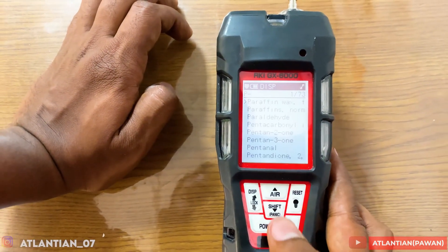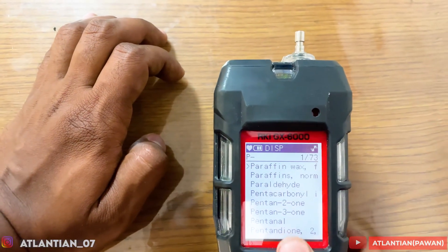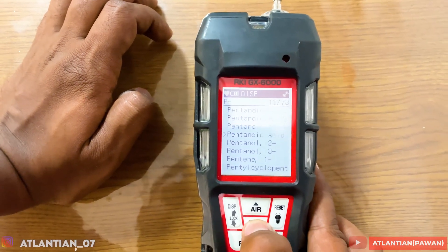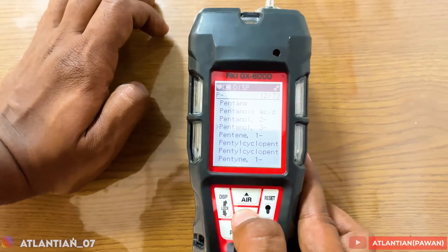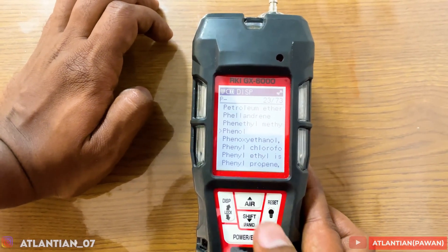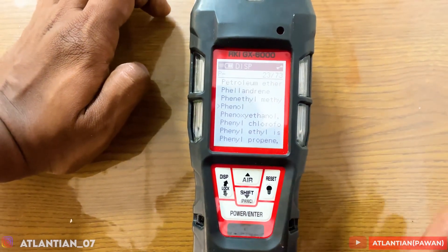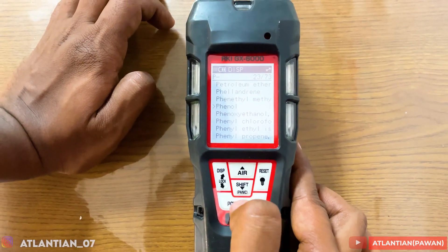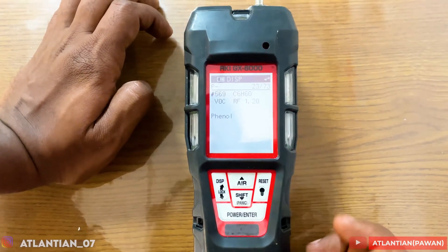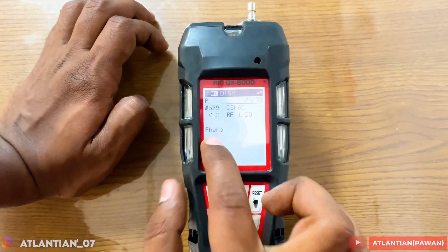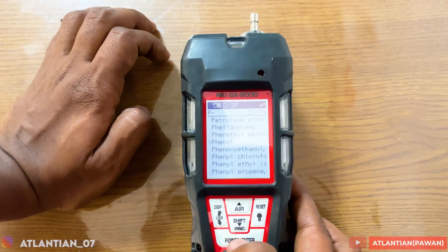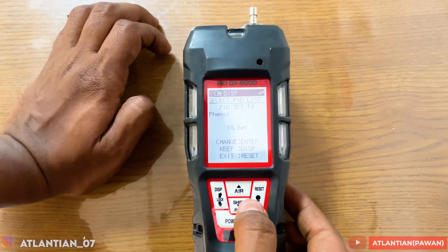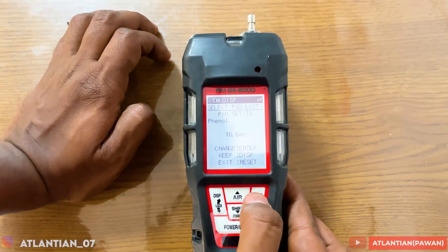Let's say you want to select a gas from P — press Enter and here you can see Paraffin Wax, Paraffin, Pentanol, Pentane and many more gases. Using the up and down keys you can toggle through. Let's say we want to select Phenol, as that is the cargo we are going to carry. I'll navigate to it, press Enter, and it will say 'VOC switch to Phenol.' I'll press Enter to confirm, and now Phenol is the gas for which it will show the reading on the main screen.